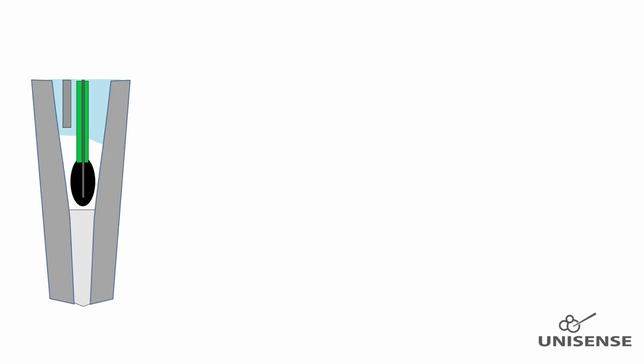In rare cases, a gas phase can evolve in the tip at the working electrode position, and such gas cannot be removed by shaking. So if there is no signal from the sensor, this could potentially be the explanation. Such a gas phase can easily be removed by inserting the tip into degassed water, which will drag the gas out of the tip through the membrane.